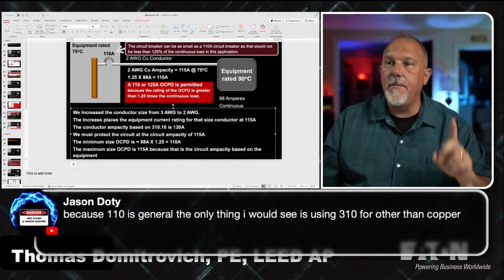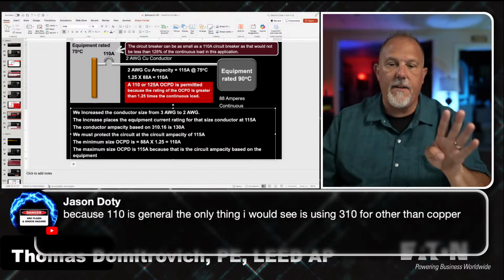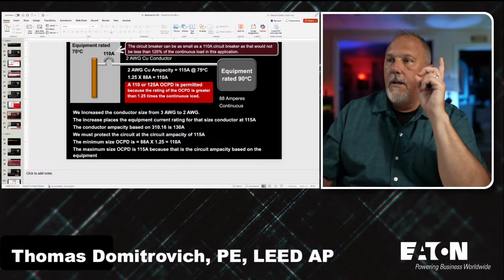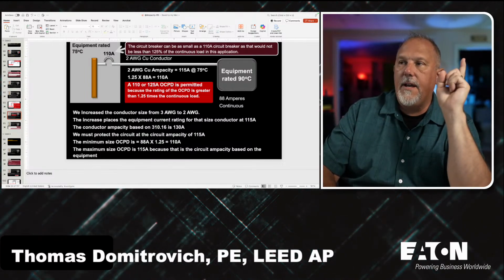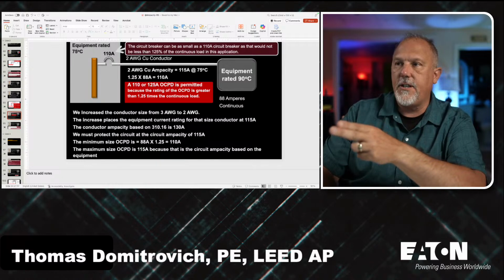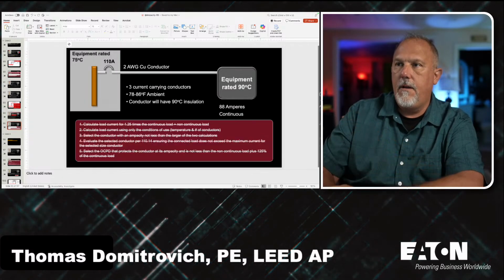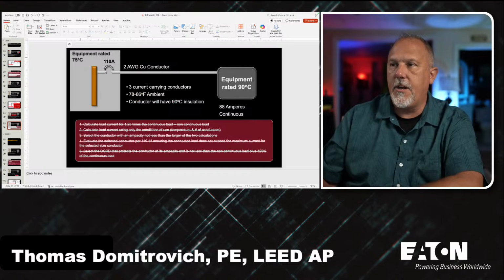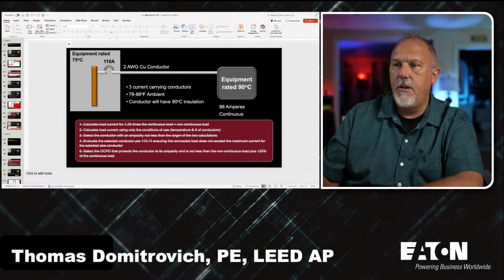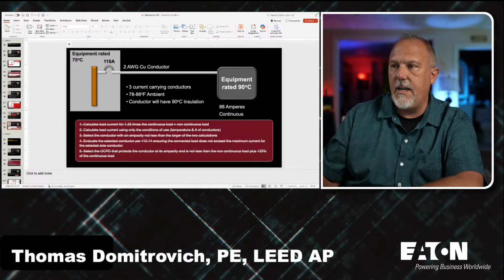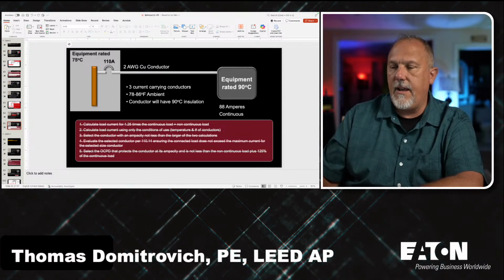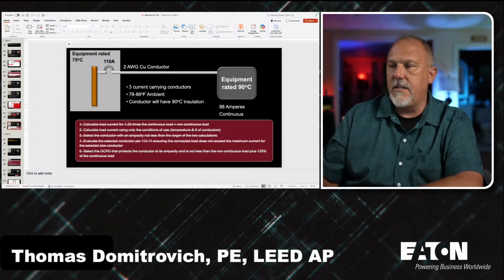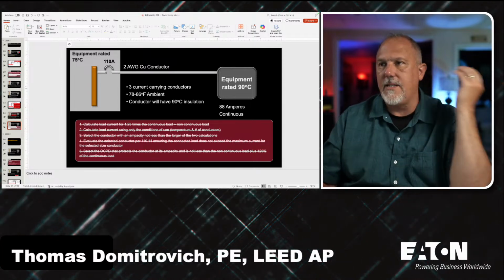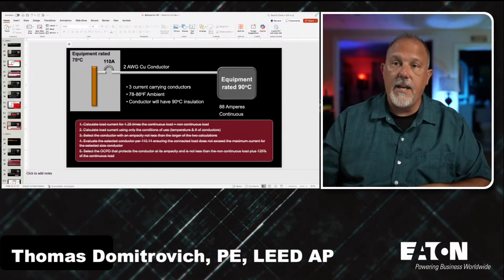Okay, I got to go through this. Hold on. All right, so let me finish this. It's 10:56, so bear with me here one second. So that means I have a 110 amp breaker with a 2-gauge copper conductor, 3 current carrying conductors, 78 to 86 degrees ambient. The conductor has a 90 degree C insulation, 88 amps, 90 degree C. That's it. So I'm at a 2-gauge copper.